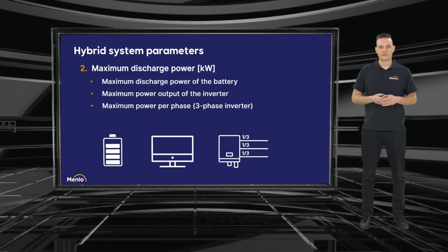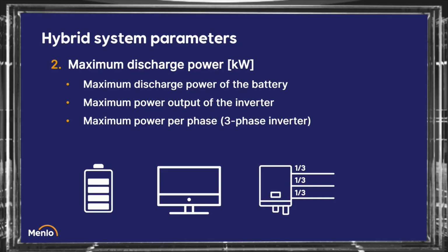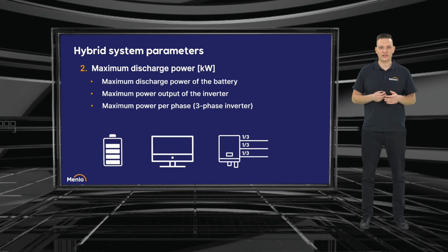Another important parameter is maximum discharge power, so how much power from the battery you can use. It will be the lowest of these three numbers. The first one is the maximum discharge power of the battery, so how fast the battery can discharge. The second is the maximum power output of the inverter. The limit can be the inverter, because its maximum power can be lower than the maximum power of the battery.